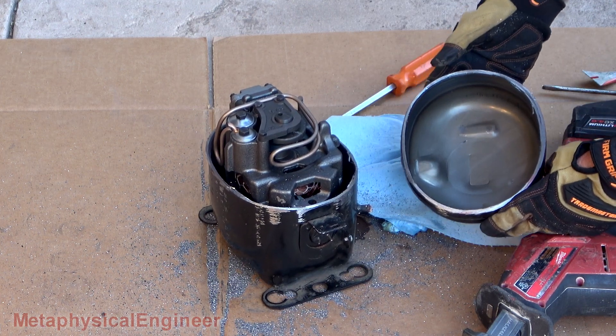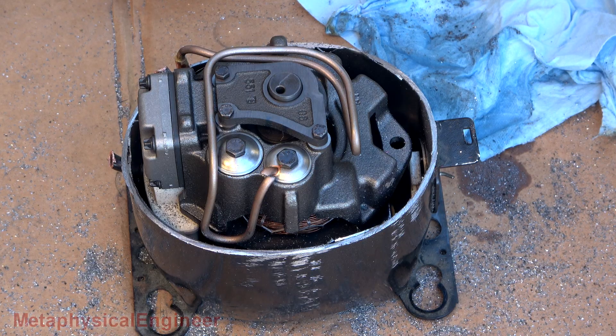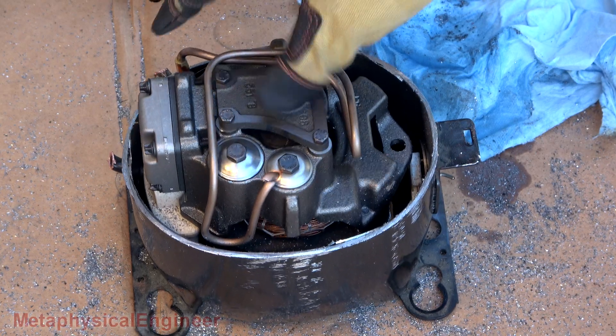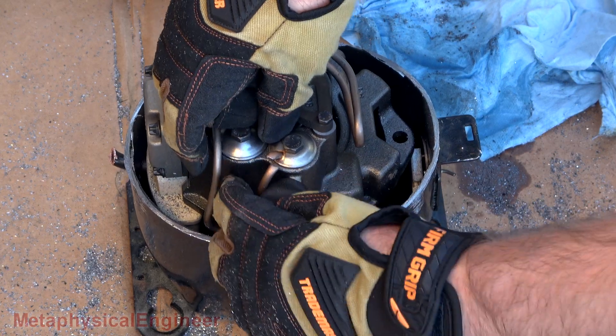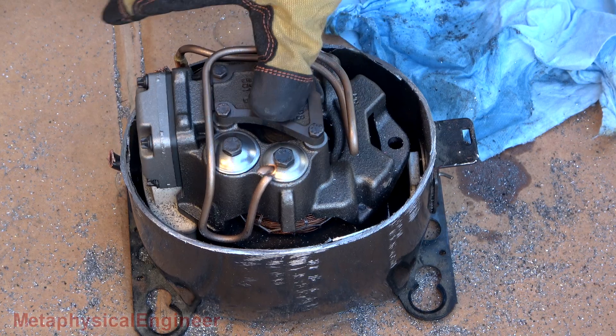There we go. Let's see what we got in here. Can anyone else spot what's wrong? I did not have a cracked discharge pipe on my bingo card, but here we are. This definitely wasn't damaged from the cut, as the cut happened way down here. This has completely detached — also explains why this thing sounded like a can full of marbles.